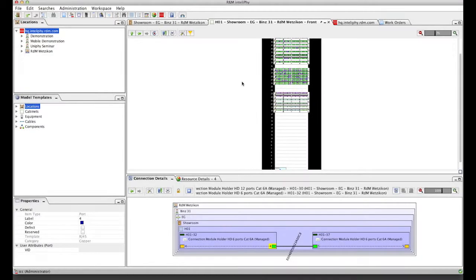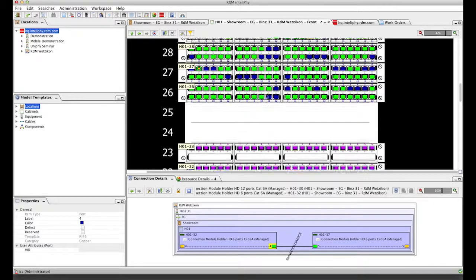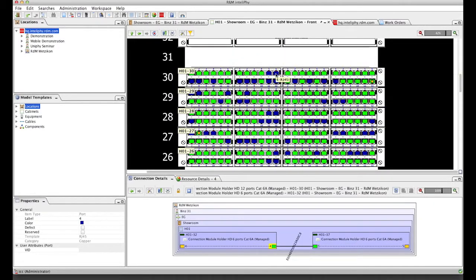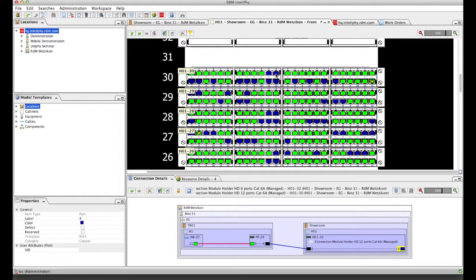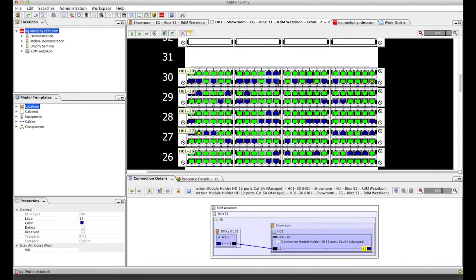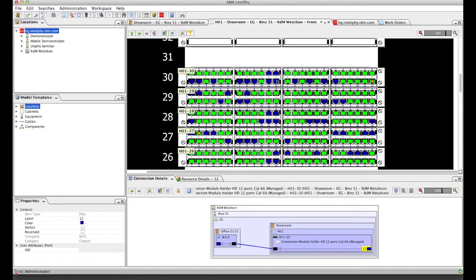Now let us see how R&M intelliPhy can automatically keep the network documentation up to date. Let's have a look at this model. At this port, I have a connection from this port to another patch panel in a different room to a switch. The port down here is connected to an outlet again in a different room. Now if I add a patch cord between this port and this port.